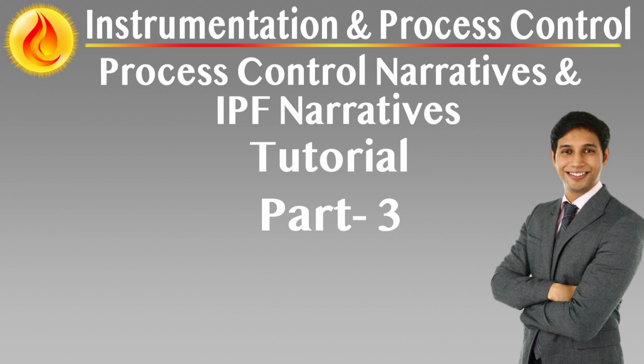Use across project phases. During the design phase, CEDs are issued alongside draft IPF narratives for review. They support HAZOP follow-ups, SIL allocation workshops, and safeguard audits. During commissioning, they are used as a reference for input-output, I/O checks, trip testing, and logic confirmation. Once the plant is in operation, they serve as a permanent reference for operators, maintenance teams, and auditors to understand how protective logic is structured and grouped. Summary. Cause and effect diagrams are foundational to the successful implementation of instrument protection systems.